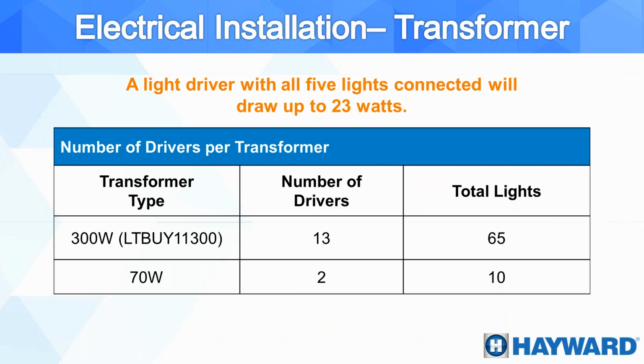So here we can see that each of these drivers is going to use up to 23 watts. Many times customers ask me, okay, how many lights can I put on a transformer? Well, that depends on the type of light that we use. Remember that we saw on some of our pool lights, they can use anywhere between 45 to 70 watts each. But these lights are so small that a fully loaded driver only uses 23 watts. And with that fully loaded driver, you are able to do 65 lights of the ColorLogic 80 on a 300 watt transformer.